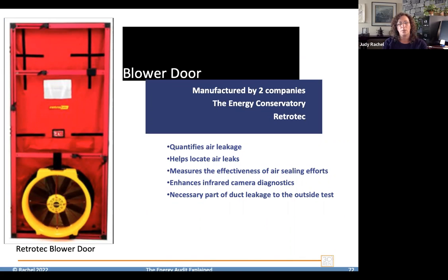So the blower door is one of our main tools that we use, and there should hopefully be a webinar on blower door testing itself in the fourth quarter. So be looking out for that. But it quantifies the air leakage, helps us locate where those air leakage paths are, helps us in our air sealing efforts to know how well we're doing, and then of course quantifies the final result of our air sealing efforts. And if you're doing duct leakage to the outside, it's a necessary part of that test.